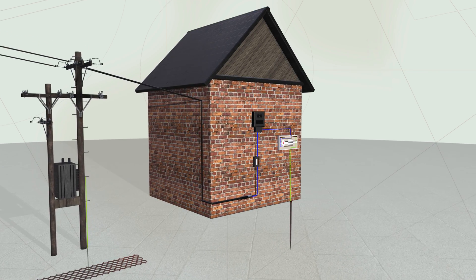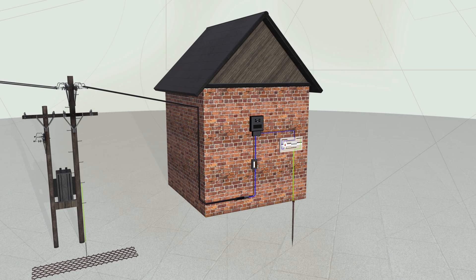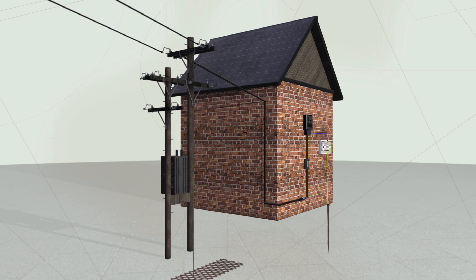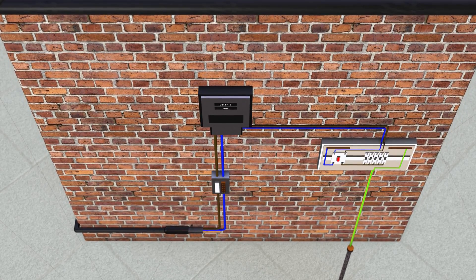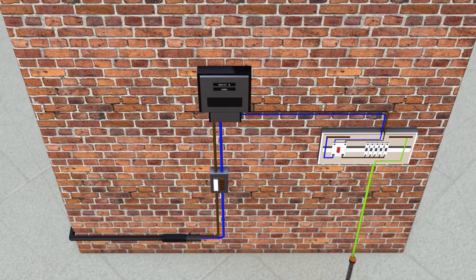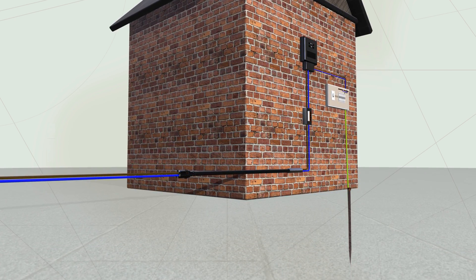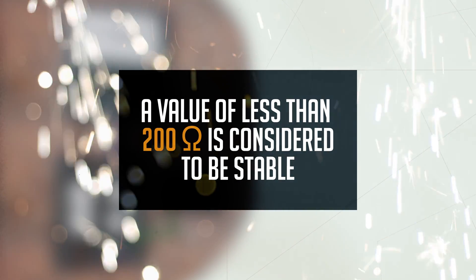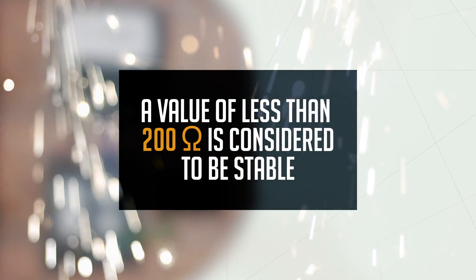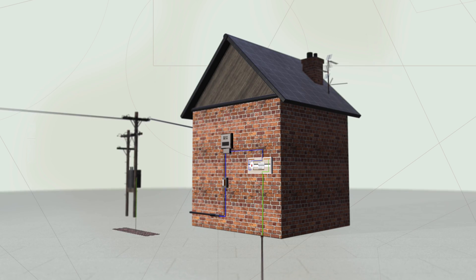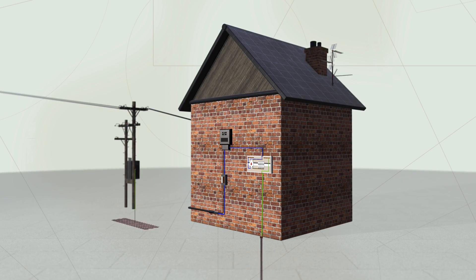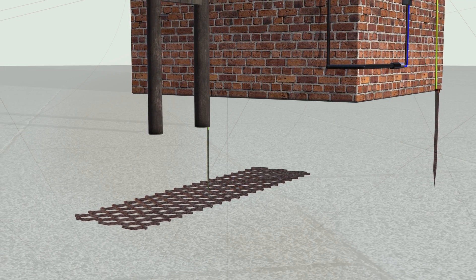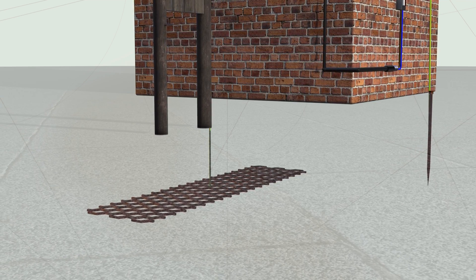In some cases, due to cost or practicality, the DNO will not provide an earth and the responsibility lies with the consumer to provide this in the form of an earth electrode. The two-wire supply to this type of installation will normally be carried via overhead cables. This arrangement is more common in rural areas where transformers are mounted on poles serving one or two dwellings. The earth conductor is connected from the consumer unit to an earth electrode driven into the ground. External earth fault loop impedance values can vary significantly, but values of less than 200 ohms are regarded as stable. Problems can arise when the ground freezes in winter or dries out in summer, so keeping the impedance below 200 ohms will improve stability.